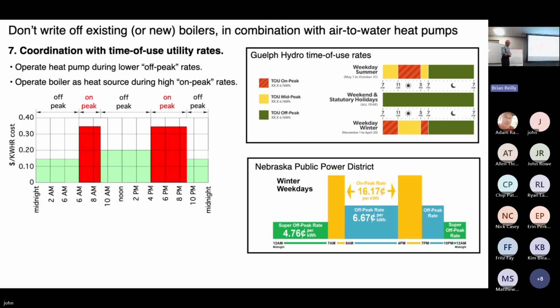There's a couple rate structures, one from up in Ontario and one in Nebraska. I just put them in as examples, but imagine we could coordinate operation of the heat pump and storage with time of use rate structures. And I'm going to show you a project here in a minute up in Maine that's actually a test bed for this, and they're getting some very impressive results up there. But the idea would be you would run your heat pump as much as possible on the off-peak rate and then put the surplus energy into storage. And then during periods when you have the on-peak rate, you would draw from storage and keep the heat pump off. That's the ideal scenario.